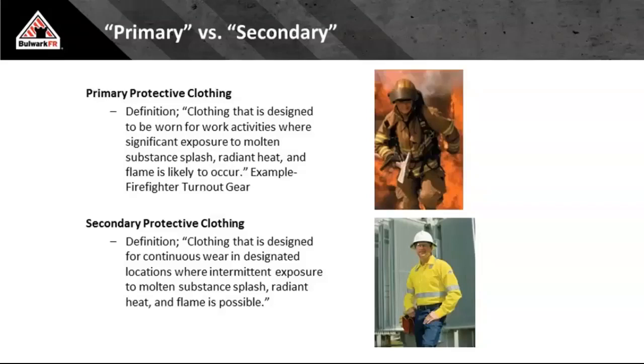We don't build electrical equipment to blow up. But when it does, we are not going to have time to go get it. Task-based daily wear programs, or task-based programs for where daily wear should be applied, are doomed to failure. I mean, just run the math. Think about it. If you're going to trust your folks to say, I have 10 electricians, they do an average of 10 electrical energized tasks a day per 70E, they're going to get in and out of their arc-rated coverall as a unit, as a group, 100 times a day. That's 35,000 times a year.